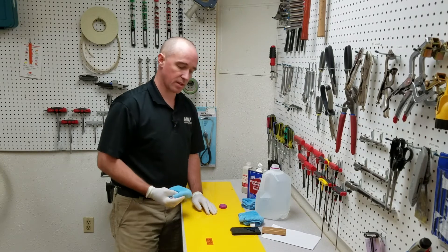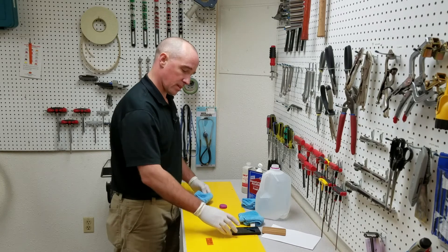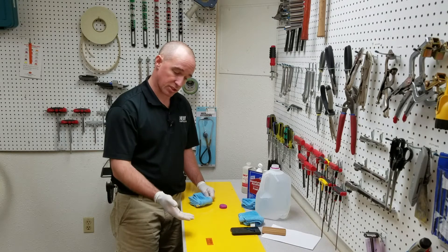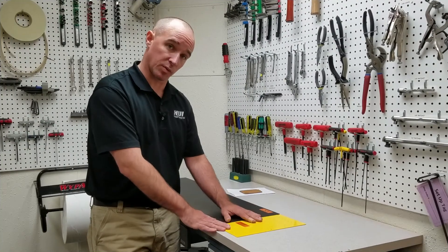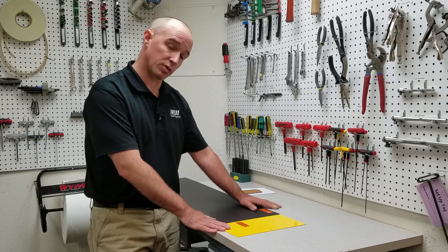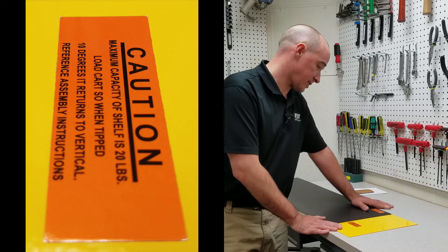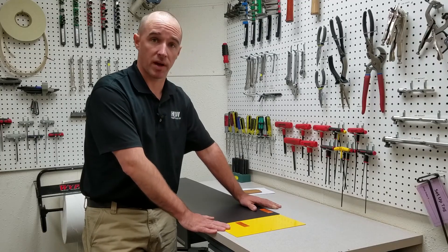I could note that one of the common strategies that we see when people are having problems with their decals failing is to just apply another decal right over the top — a clear decal — so it looks good. We're going to come back in 24 hours and make sure that hasn't changed it, that you can still clearly read it, and that the edges haven't started to peel up. So here's the decal that we just performed the test on. This particular decal up here we did yesterday, so it's been over 24 hours. When we examine the decal, the edges are still flat and you can't tell that there's any damage whatsoever, so this would be a pass. That is how we conduct the Marking Durability Test for your custom medical cart. Thanks for watching.